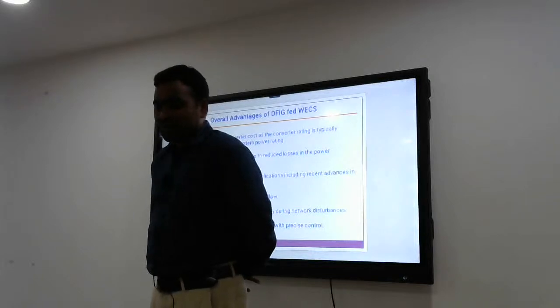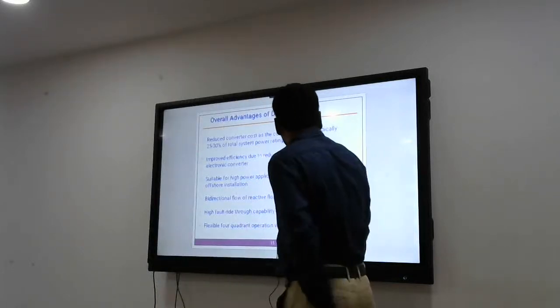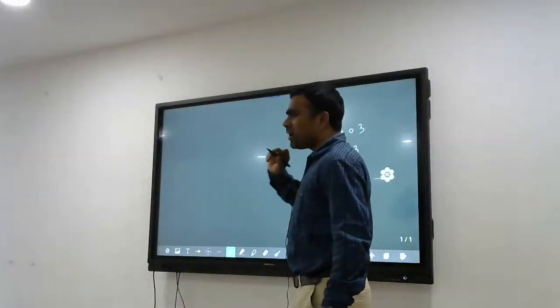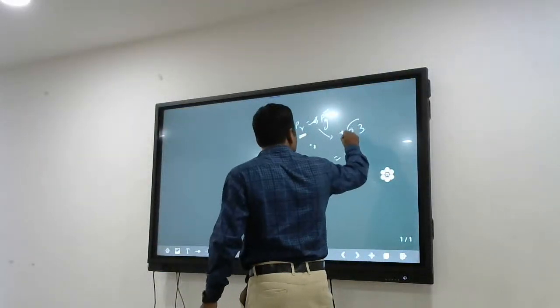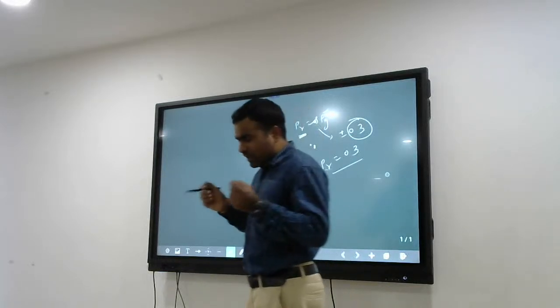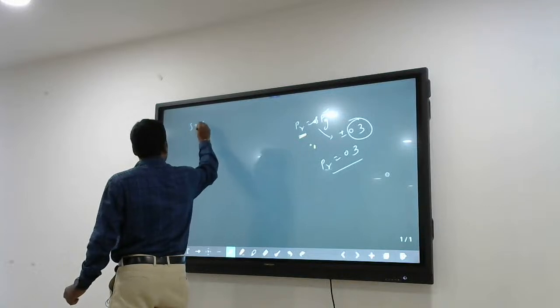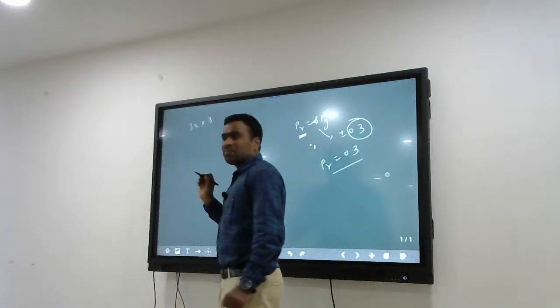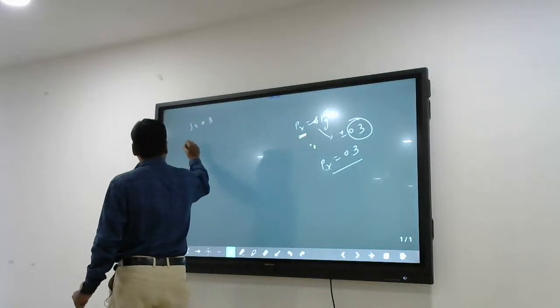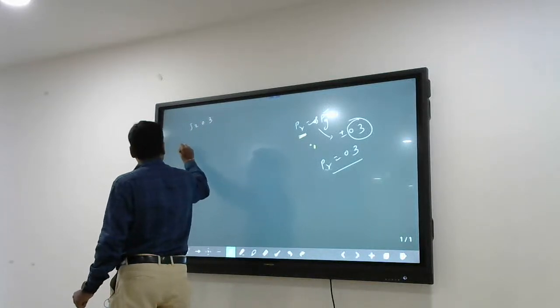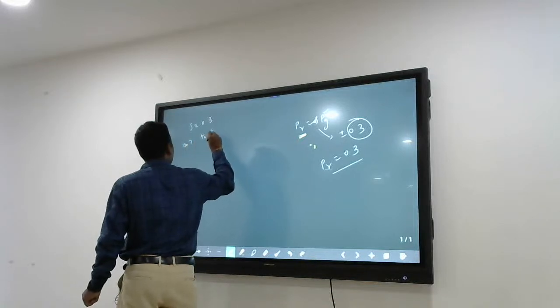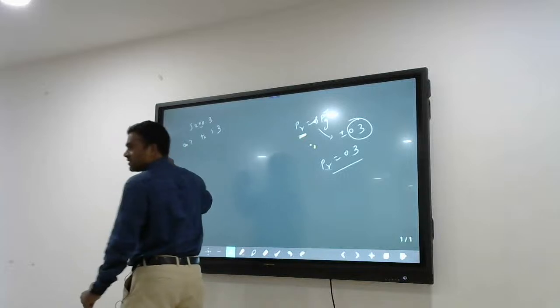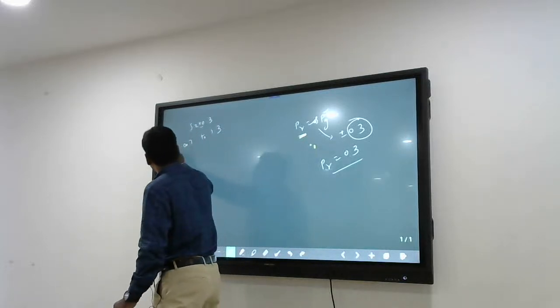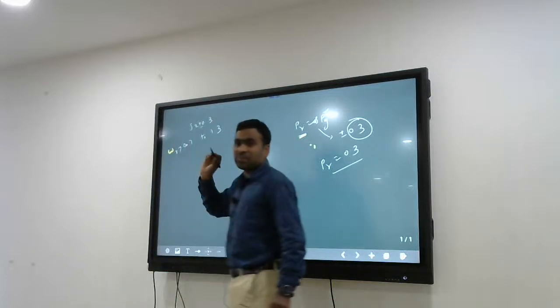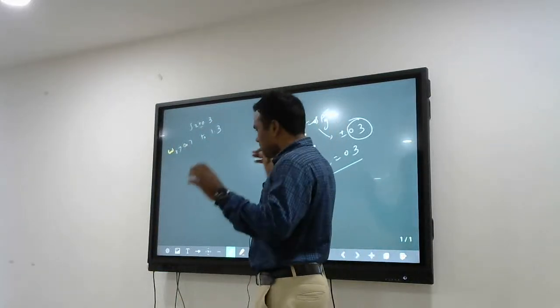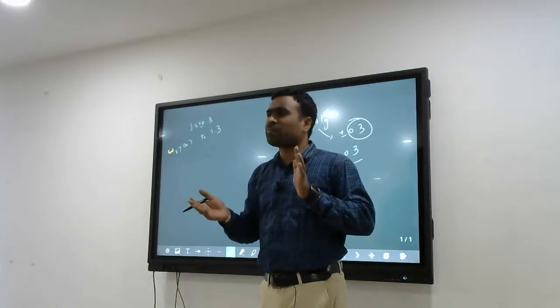Here I think one point you have to clear. I told 0.3 per unit, I fixed it. Why have I restricted my slip to 0.3 only? Slip is 0.3 means the speed is 0.7 to 1.3 per unit. Suppose my slip is plus or minus 0.3, then my rotor speed is 0.7 per unit to 1.3 per unit. I told my machine will run only in this 0.7 per unit to 1.3 per unit range.